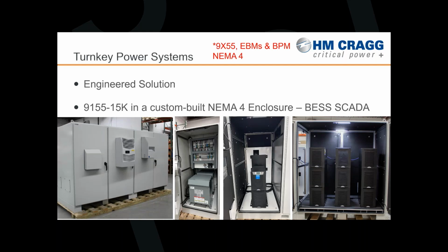These pictures show a 9X55 system we shipped last year—a 15K UPS system with 3 extended battery runtime modules. What was unique about this project is that it was supporting a utility scale battery energy storage system, providing critical backup power for their SCADA and control systems. It was a very small load, not taking the full 15 kVA of the UPS—right around 2 to 3 kVA—but this provided nearly a day and a half of runtime.